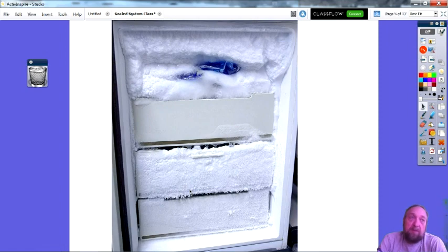Yes? No? Yes, it can. Actually, no, this is not a defrost problem. This is a door seal problem where warm air is getting in, because in the middle and up and around here, there's no evaporator. The evaporator is behind these shelves. A defrost problem wouldn't make ice go all the way from the back of the freezer to the front where the door seals.